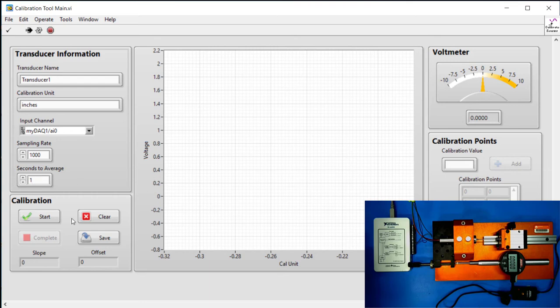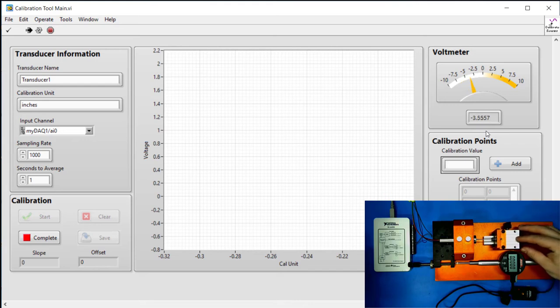Now we're ready to start a calibration, so you click the Start button. The voltmeter in the upper right here shows you the current voltage sensed by the system from the transducer. So we're going to move the core until that gets very close to 0. And that's plenty close enough. We're talking within 100 millivolts or so. And I'm going to lock that down so that the core does not move.